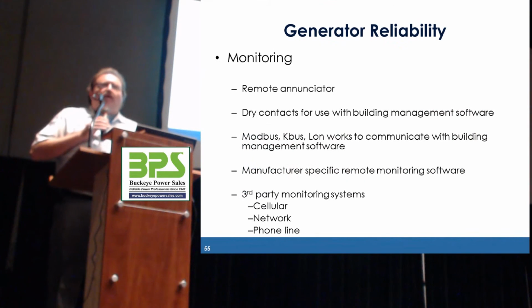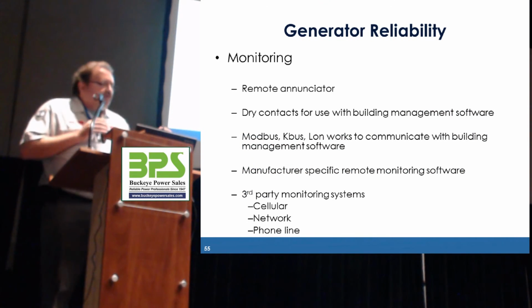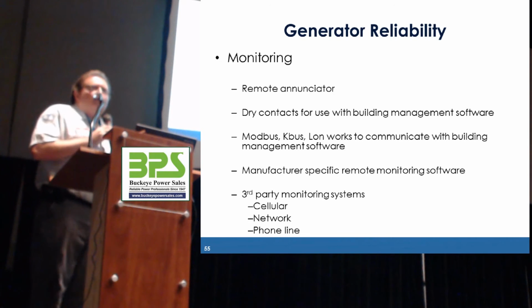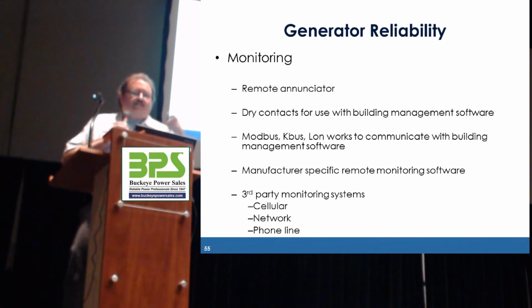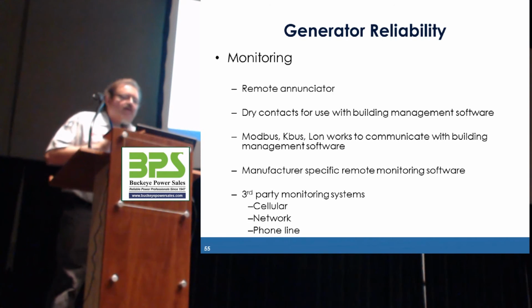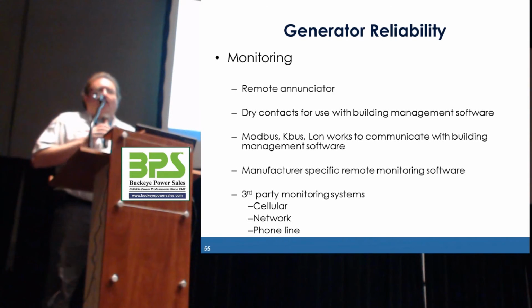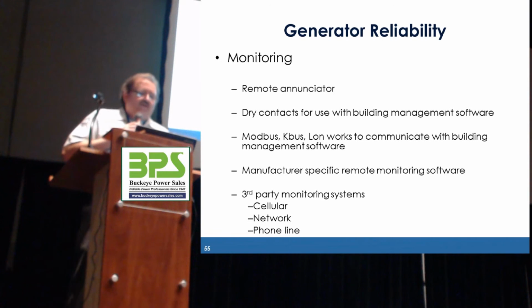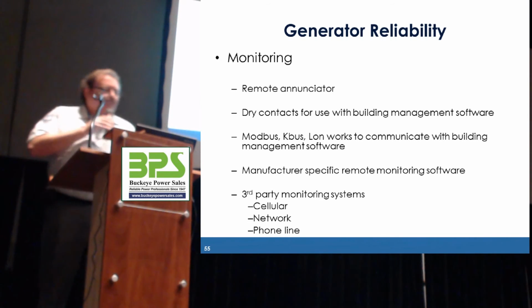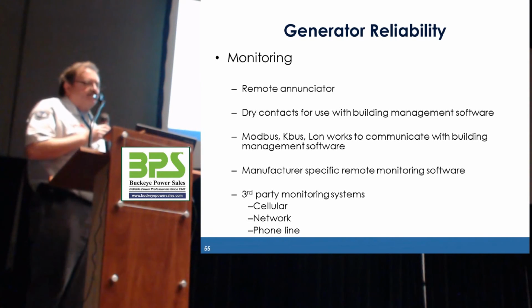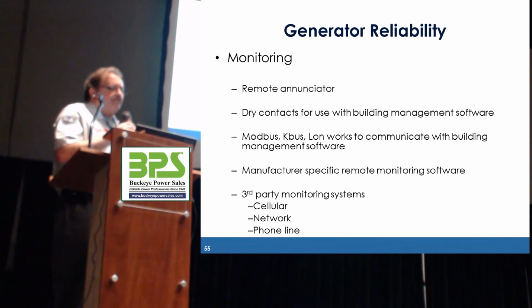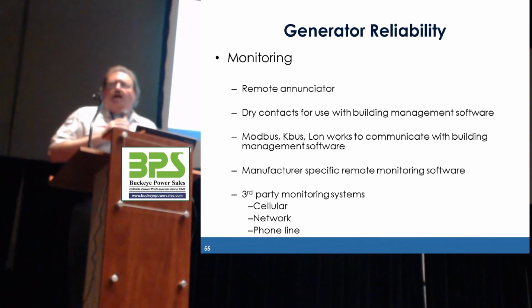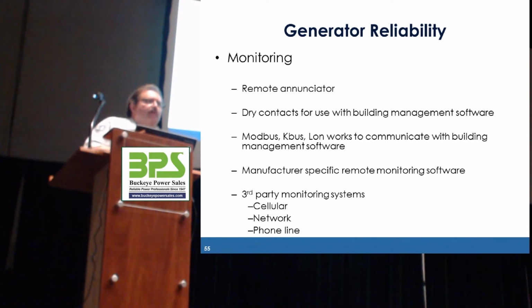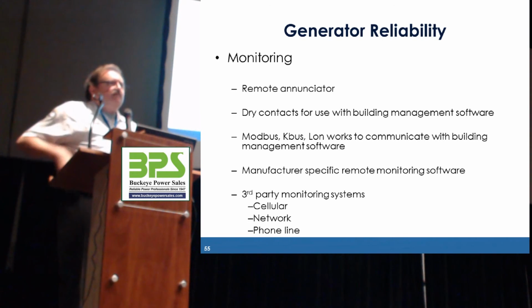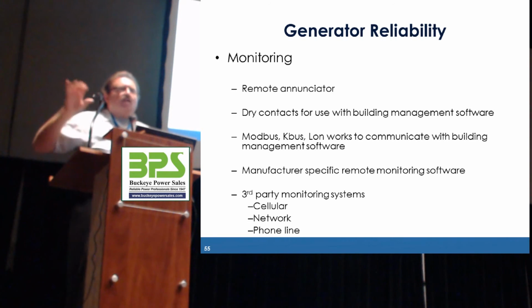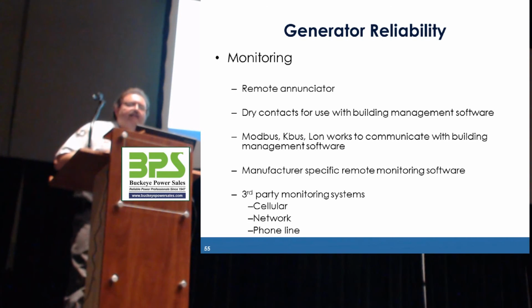And then the last part is your monitoring, whether it's as simple as the remote annunciator, whether it's an old system of dry contacts that's tied into your building management, whether it's using some sort of protocol like Modbus or KBus that ties in, a manufacturer-specific software, or there's a number of third-party people out there that have monitoring devices. So whenever the generator runs, it sends you an email, sends you a text to your phone, generates a log so that you have that in addition.